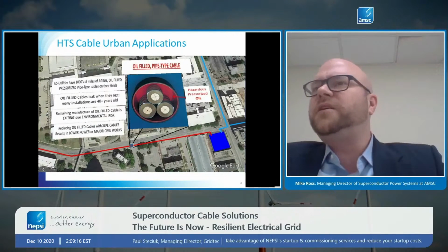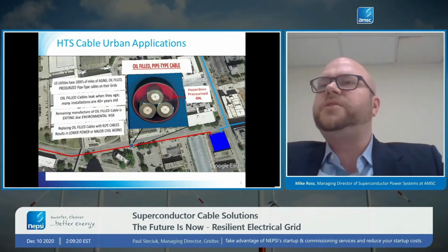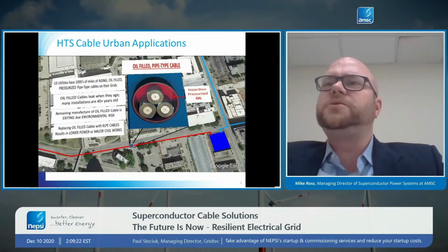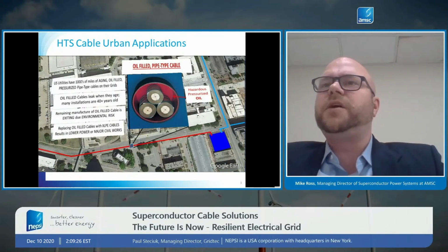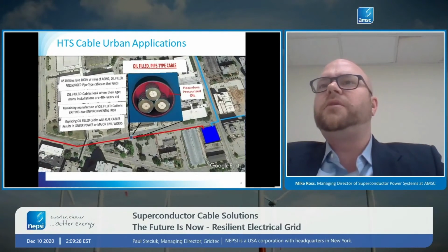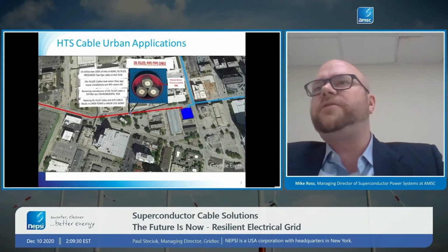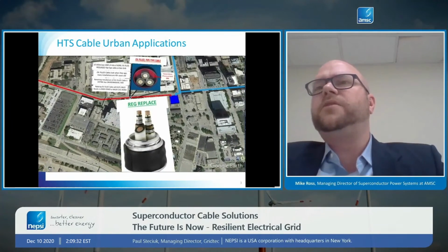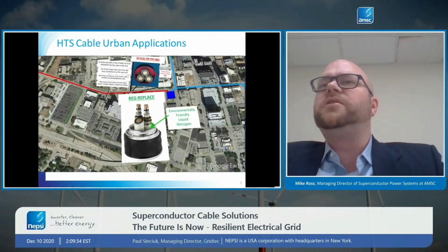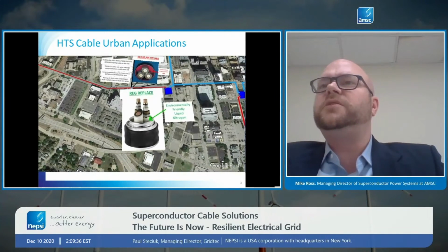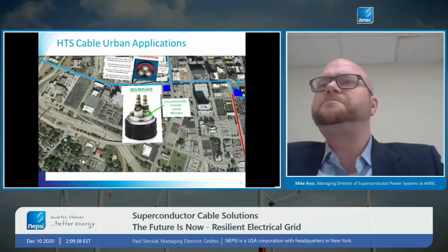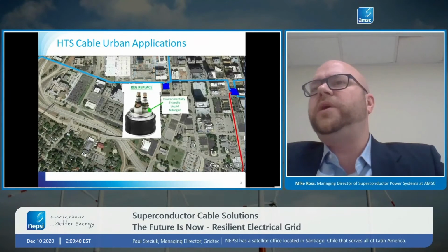And this is a technology that's becoming quite old. A lot of them have been around 40 or 50 years, and they're filled with oil that, if they leak, creates environmental hazards. The entire industry is moving away from this type of cable, and there's really only one vendor left in the U.S. that makes this type of cable. So utilities are trying to move away from it.